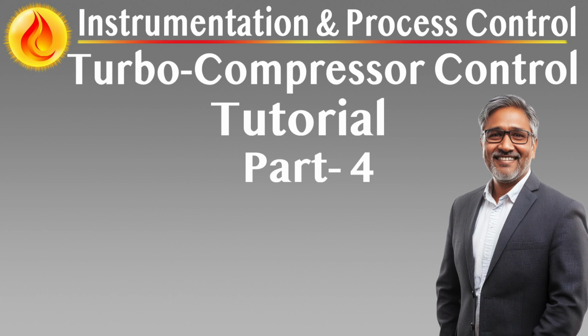Software interfaces and data sharing. External system integration. The TCCS interfaces with Distributed Control System DCS via OPC Modbus TCP, Emergency Shutdown System ESD via hardwired I/O, Motor Control Centers MCC via relay logic and status inputs, Condition Monitoring System CMS via Ethernet or serial links. Interface mapping. The vendor collaborates with other package vendors and the owner to define memory blocks and communication structures, establish signal ownership, timing, and responsibility, coordinate time synchronization and SOE alignment.